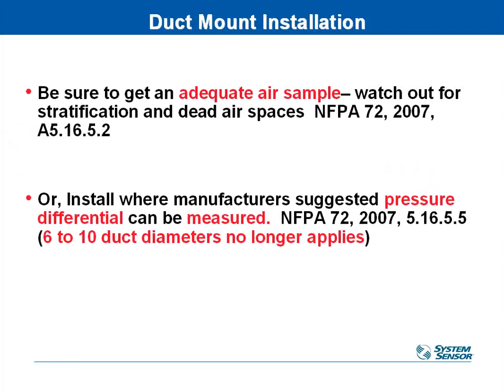So the old NFPA required 6 duct diameters downstream. Now the new current NFPA 2007 version just says you have to get an adequate air sample. And the reason for that is you want to make sure you don't have your tube in places that are dead, like the corner of an elbow, or where they are stratified, like coming through a fan or something like that. The exception to that is any place that the manufacturer of a packaged equipment, if you're mounting it in the packaged equipment at the factory, says that you can, based on their measured pressure differential. You can also do it in the field that way.